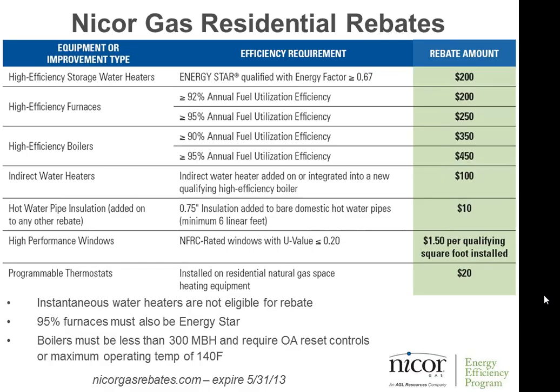Real quick, I just wanted to touch on some of the rebates that are involved with these boilers before we continue on with snowmelt discussions and things like that. I'll show you some residential and commercial rebates that tie into these boiler systems. So specifically for right now, for Nicor, we'll hit the other utilities in a second. Nicor has 2 residential rebates available for boilers. It's 90 and 95% of the 2 tiers, and that corresponds to $350 and $450 rebates you can get residentially. You do have to have outside air reset controls, which come standard on most condensing boilers anyway, so that's pretty easy to do, and the radiant system will do well with the outside air reset schedule.